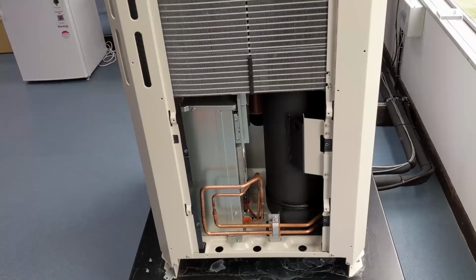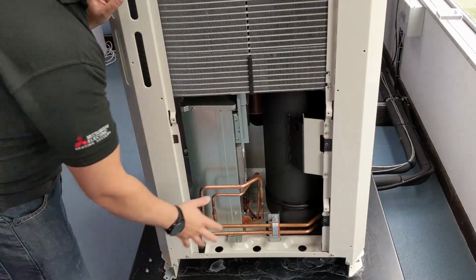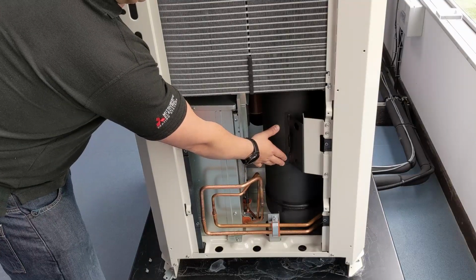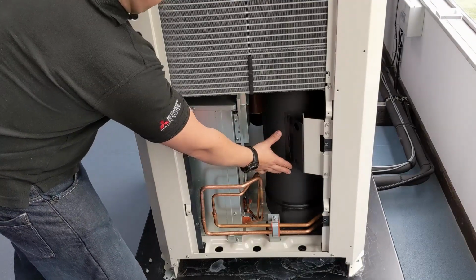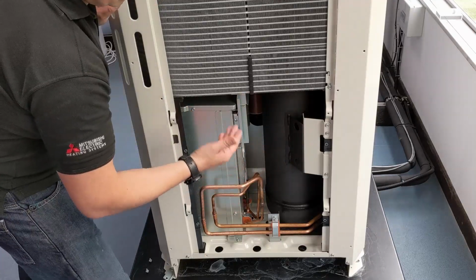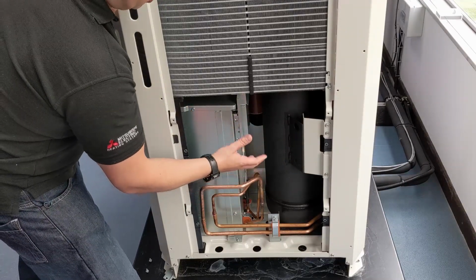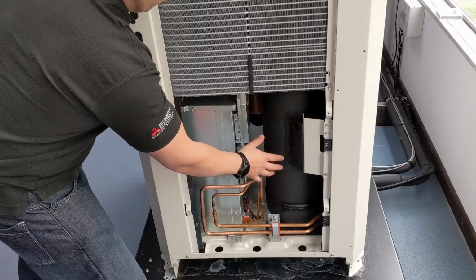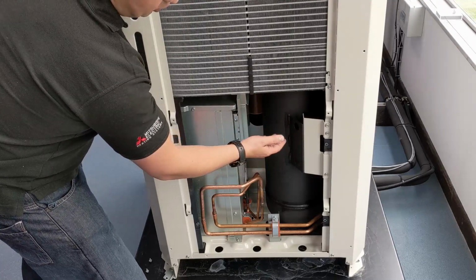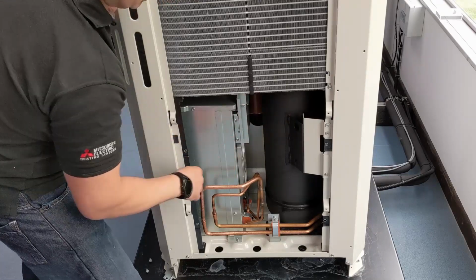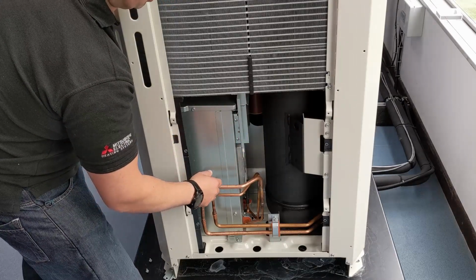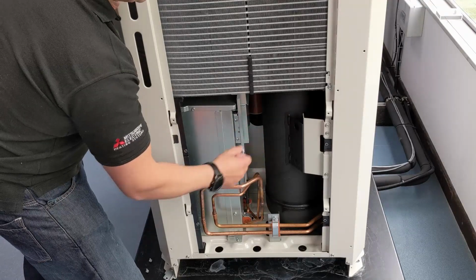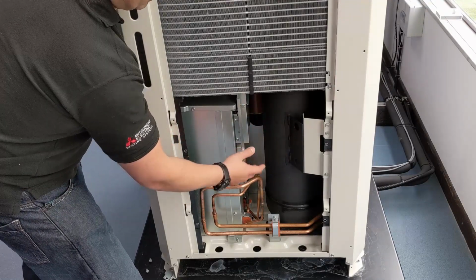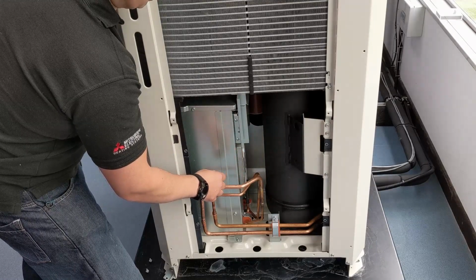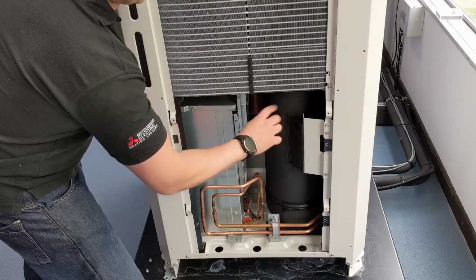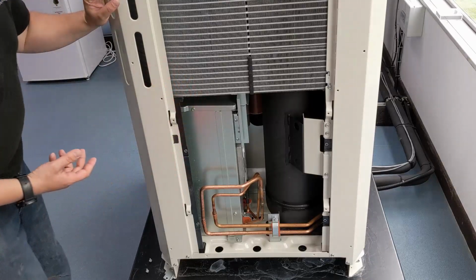As that refrigerant comes back to the outdoor unit, next thing it comes to is an accumulator. This is acting as a buffer vessel, because at the end of the day we're ramping this system up and down, therefore we're not going to need all that refrigerant at all times. But it's also acting as a way of making sure that we've got vapor getting taken off the top of this, off to the compressor, so a bit of protection to make sure if there was any liquid to come back from the indoor units, it's not going to damage the compressor. We're also using it as a way of drawing some oil back for the actual compressor as well. So from the accumulator, off to the compressor, and then we start that refrigeration circuit all over again.